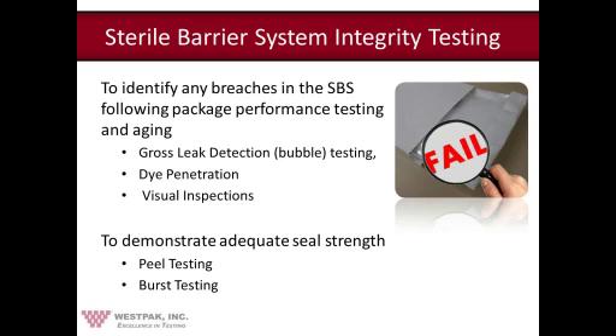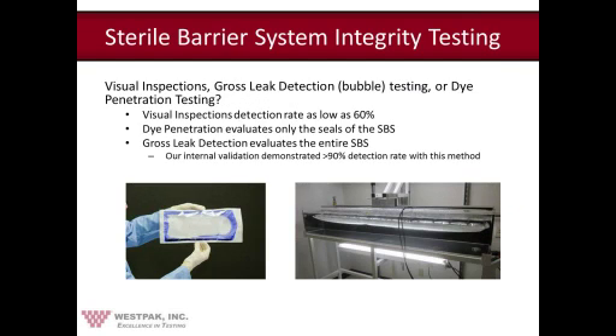Typically, bubble testing, dye penetration, and or visual inspections are used to do this. ISO 11607 also says that you need to demonstrate adequate seal strength of your pouches and trays. So typically, peel testing or burst testing is done for this. We've seen many protocols in the industry, and a lot of times companies will call out either visual inspections, bubble testing, or dye penetration testing, or some combination of the three.